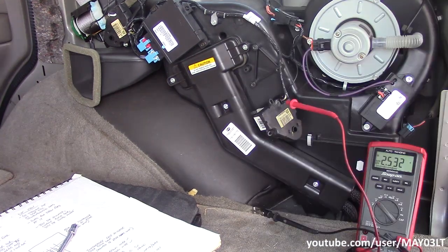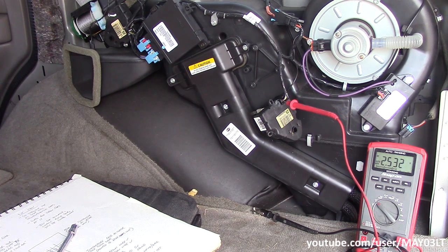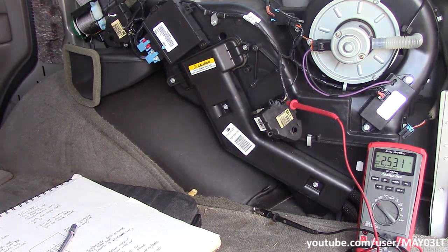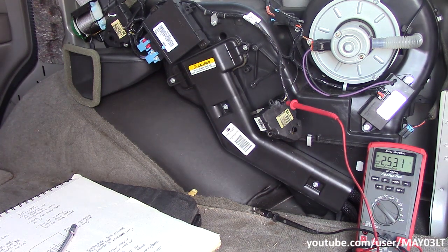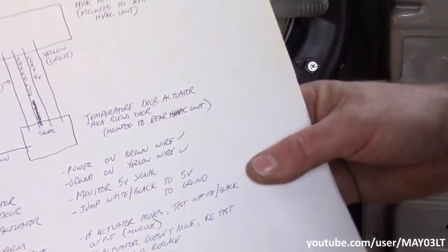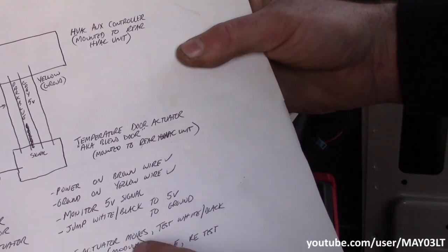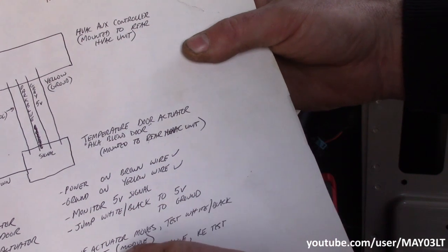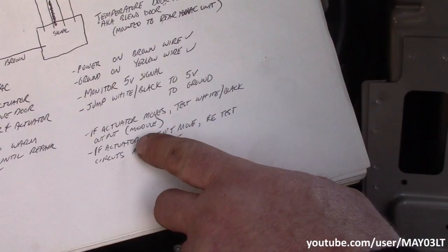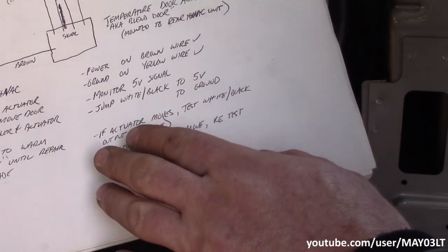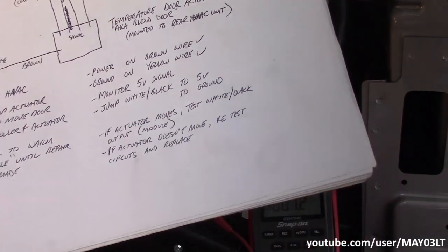We're at 2.5 volts, the temperature is all the way at hot. Let's see if it changes if we go to cold. And it didn't change. Going back to our information, if the actuator moves, test white black output, and that's from the module. We didn't have any, no matter what we did. So that tells us the module itself is bad.